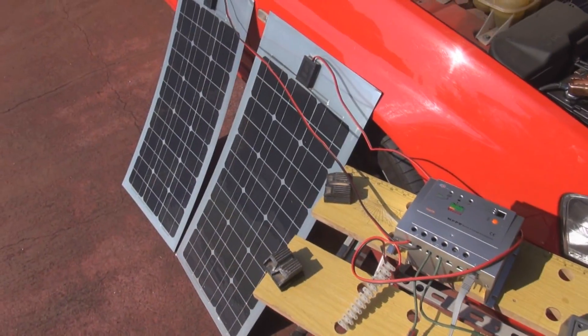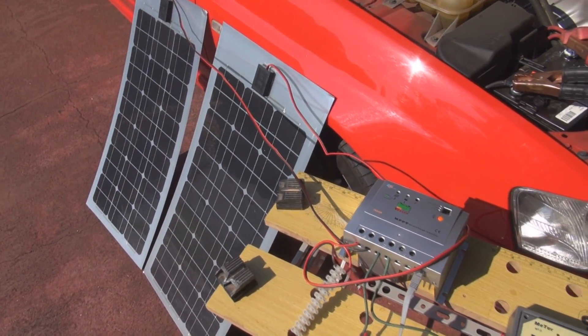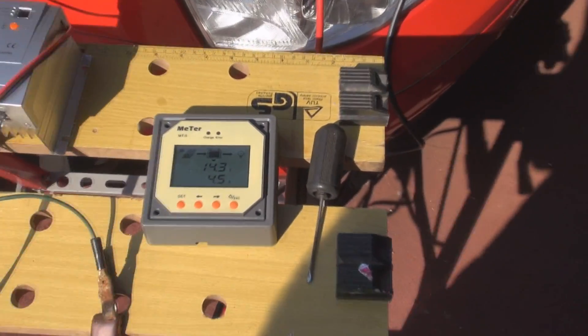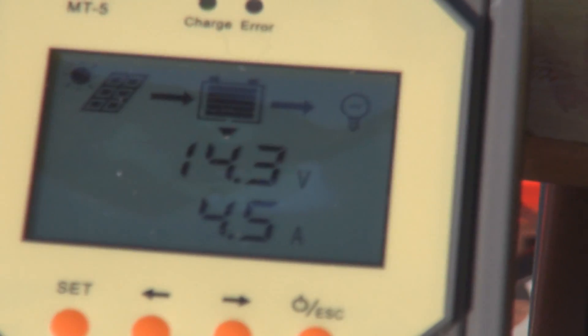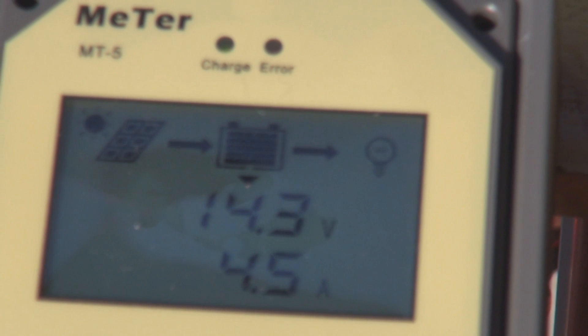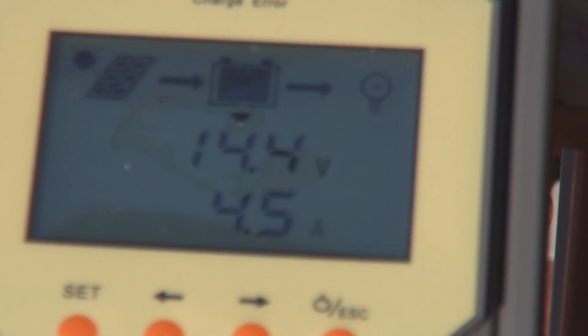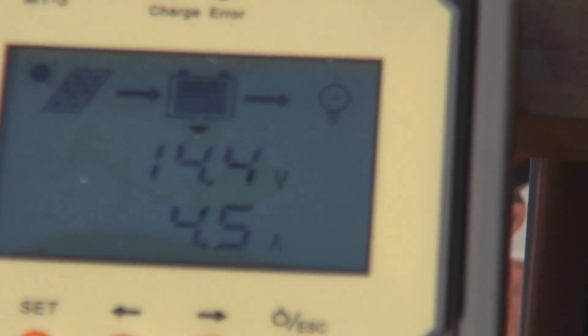The system has been charging now for about half an hour. Without the load on the battery, the voltage has steadily increased as the charger pushes towards its maximum boost voltage, which is around 14.4 volts, which it just hit.